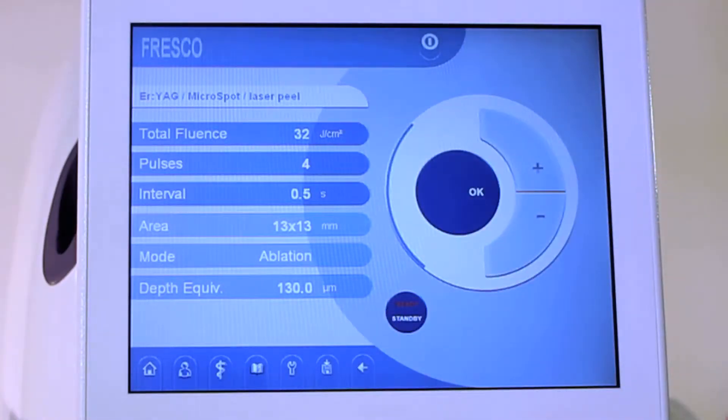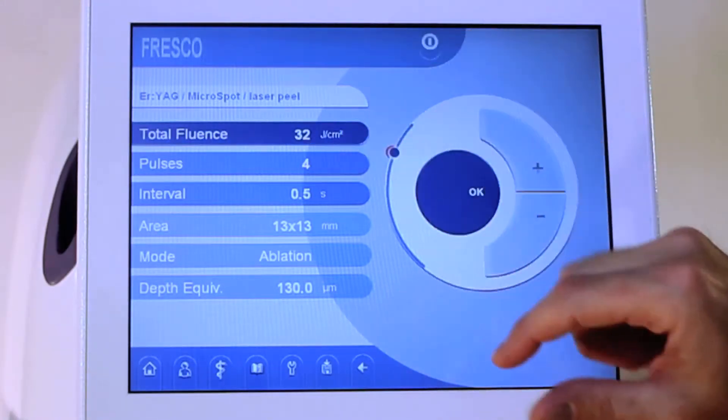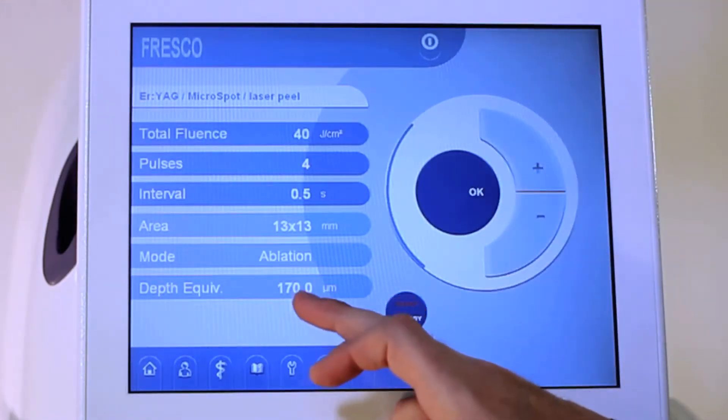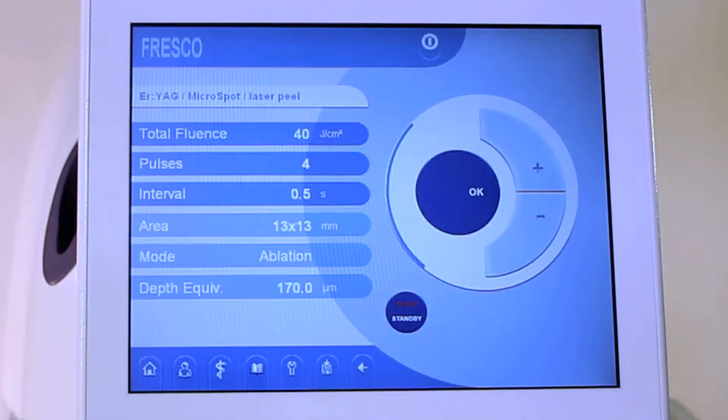We obviously haven't changed the total energy. If we want to change the energy, again, same thing. You tab it up. You must hit OK. That saves it, and again, it then automatically adjusts what your depth equivalent will be.